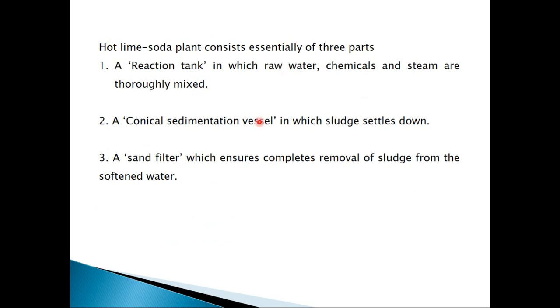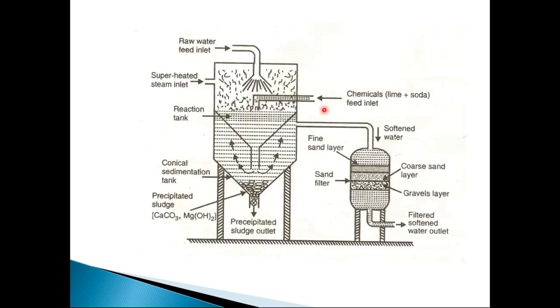Since you are heating the water, if carbon dioxide is present it is driven out. When you increase temperature, viscosity decreases, so if your water is too viscous, the hot lime-soda process will also decrease viscosity. The residual hardness in hot lime-soda process is 15 to 30 ppm, which is comparatively lower than the cold lime-soda process.